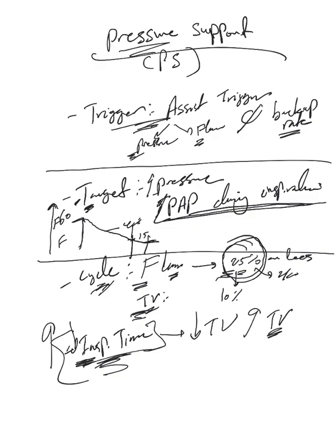The last thing I want to finish: in pressure control and volume control, the patient cannot alter his inspiratory time. It's already predetermined. But here the patient can change his inspiratory time, and of course tidal volume accordingly, from breath to breath.